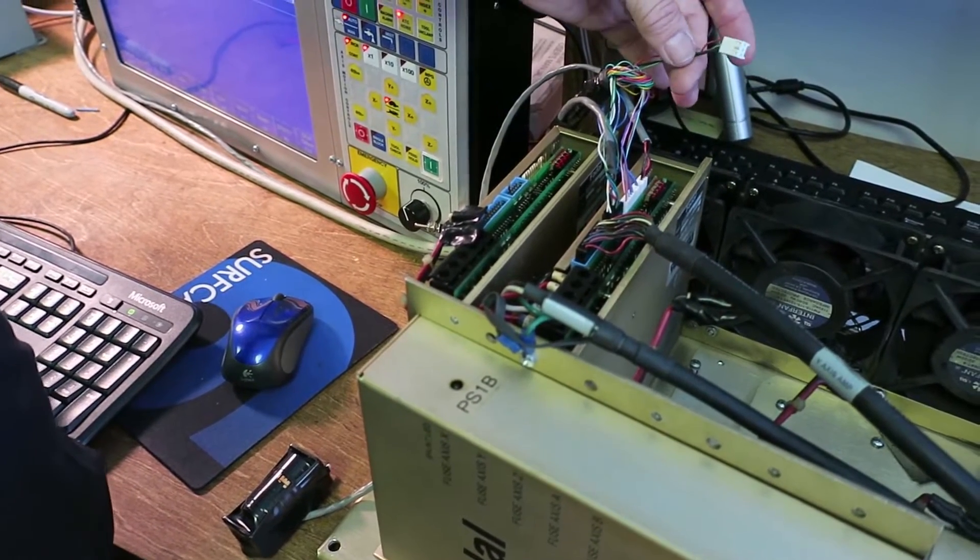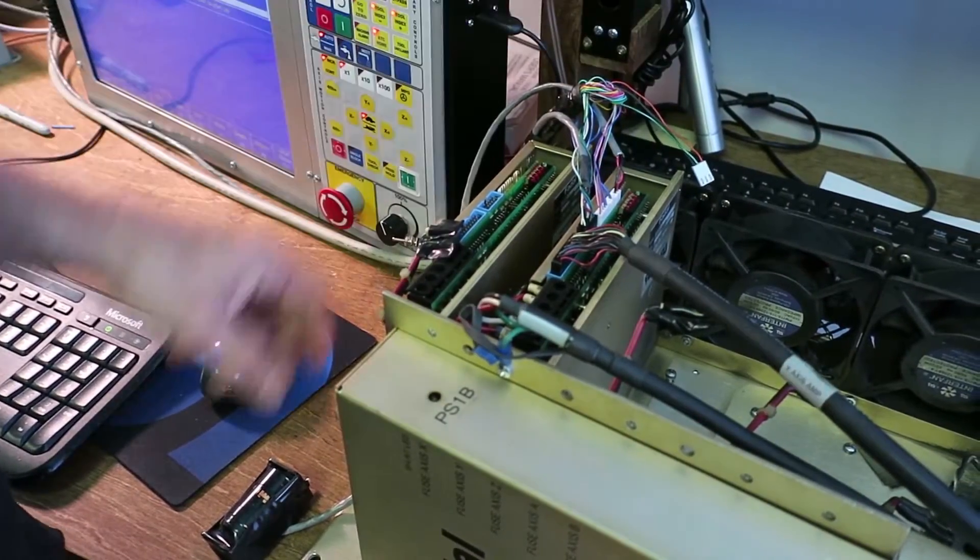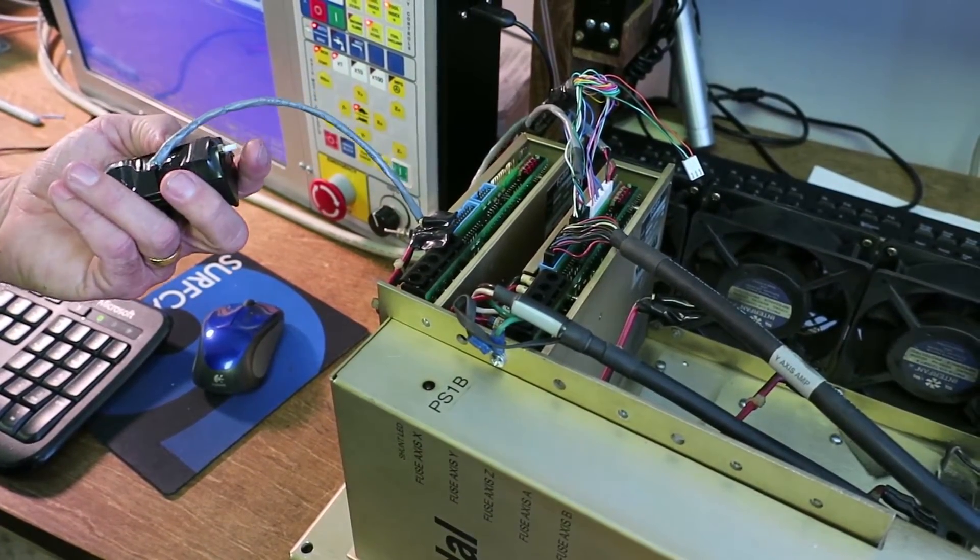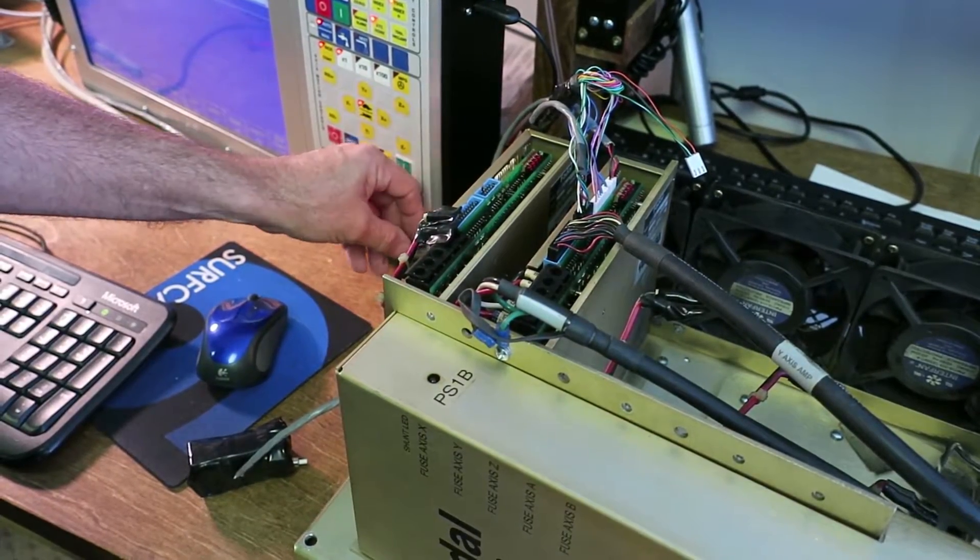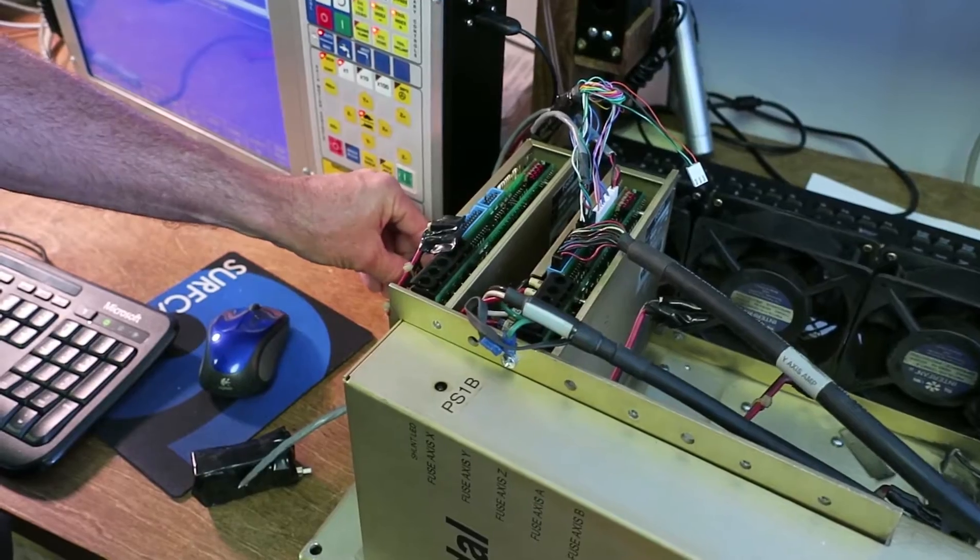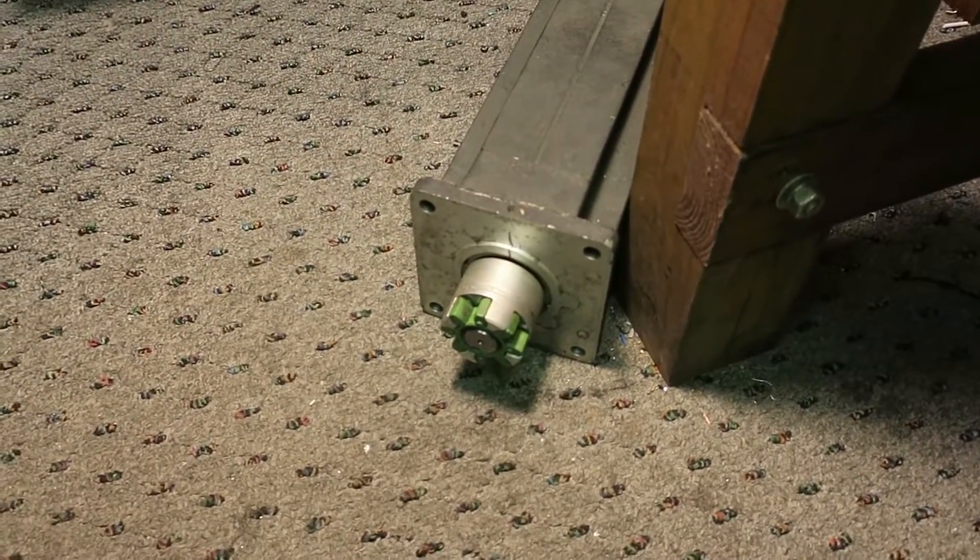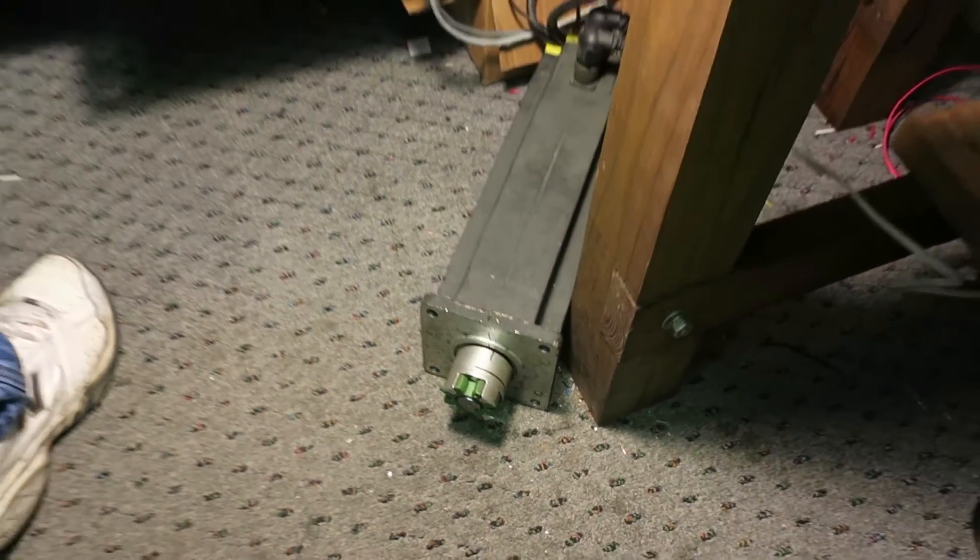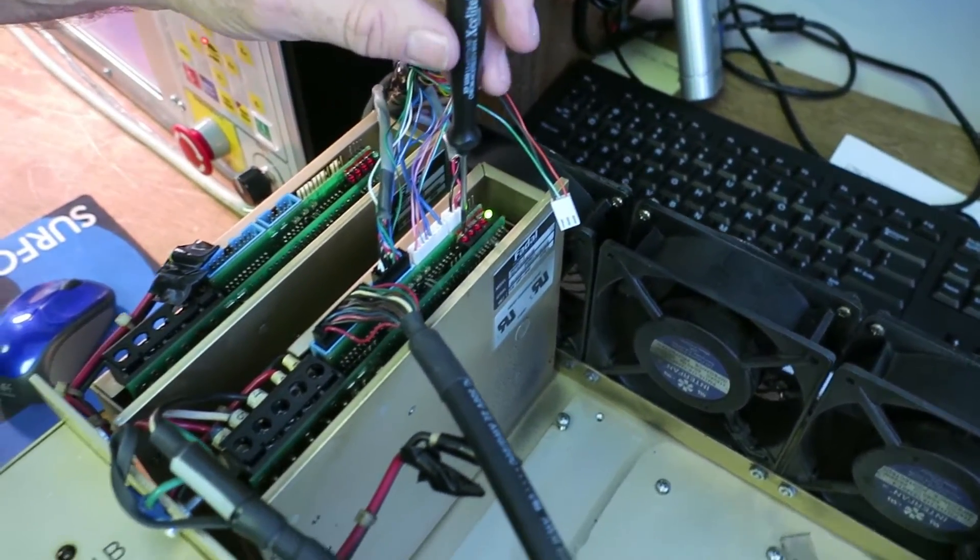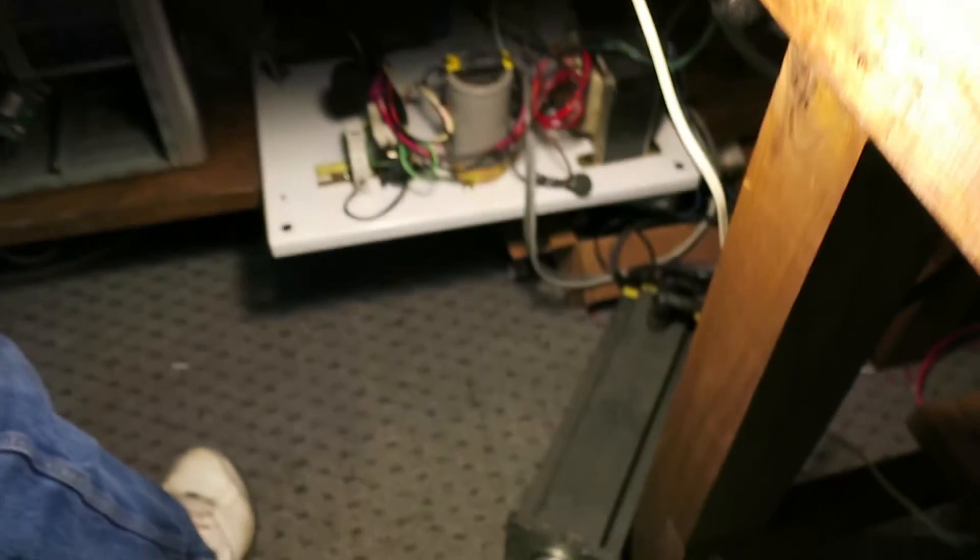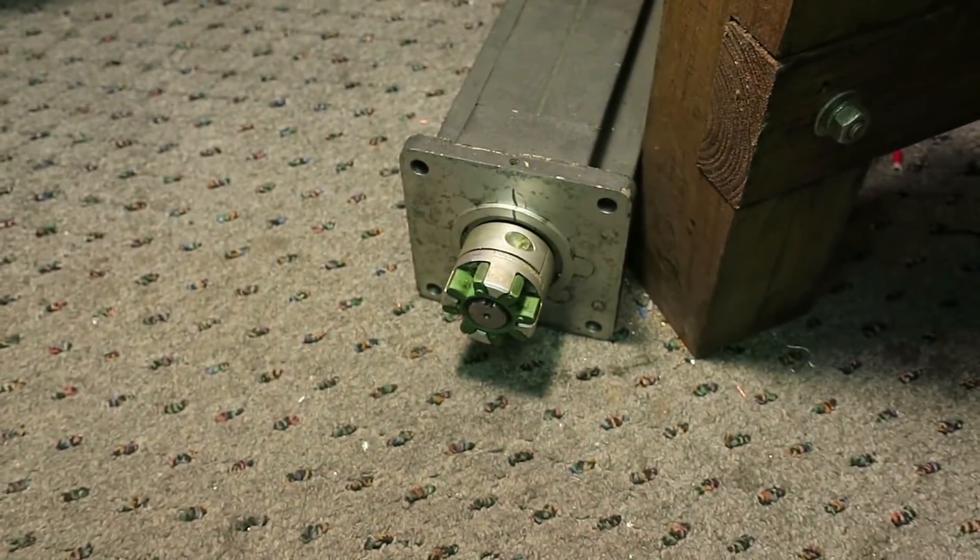So the few things that we're going to do with that, we've got it all set up now. I've disconnected the centroid command, and I've tied in my own command to the drive. It's just a little battery box. So we're going to use step commands to it. The first thing I'm going to do is I've got zero command to the drive. I'm going to enable the servo drive. You can see the motor is drifting because the balance is not set right in the drive.